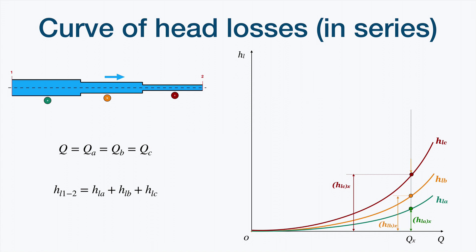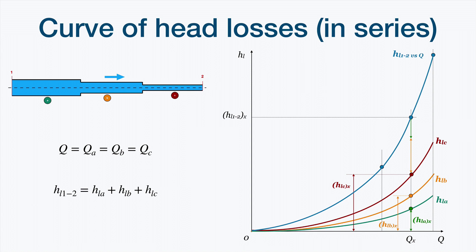Let's add the values starting at the pressure losses for pipe C, then add the value for pipe B, and then the value for pipe A. We will obtain the total pressure losses — the overall pressure losses between section 1 and section 2 — for this value of flow rate QX. We will do the same for another value of flow rate to obtain the overall pressure losses for that value. And the same for yet another value. Finally, we can draw the overall curve of pressure losses between section 1 and section 2.